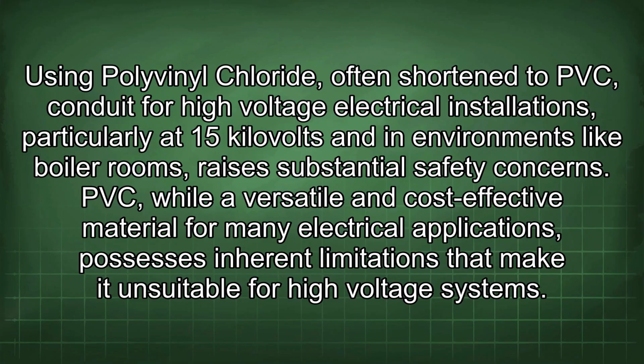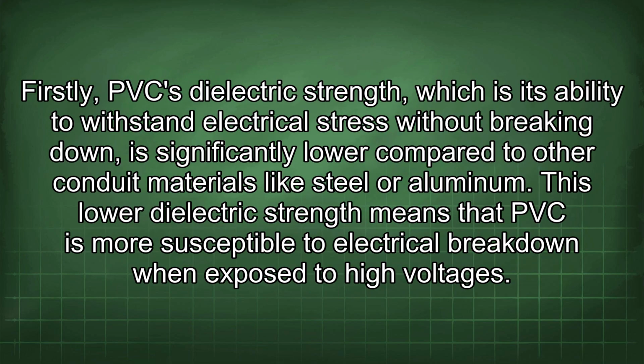Using polyvinyl chloride, often shortened to PVC, conduit for high-voltage electrical installations, particularly at 15 kilovolts and in environments like boiler rooms, raises substantial safety concerns. PVC, while a versatile and cost-effective material for many electrical applications, possesses inherent limitations that make it unsuitable for high-voltage systems. Firstly, PVC's dielectric strength, which is its ability to withstand electrical stress without breaking down, is significantly lower compared to other conduit materials like steel or aluminum.